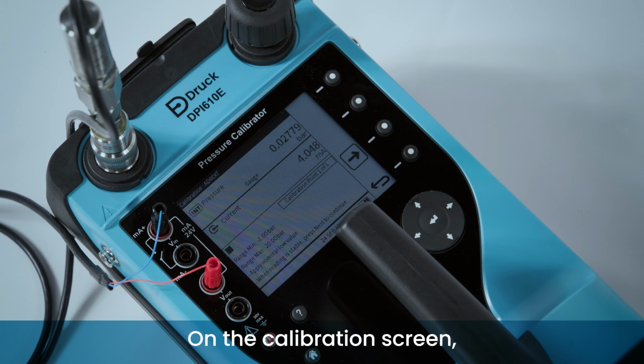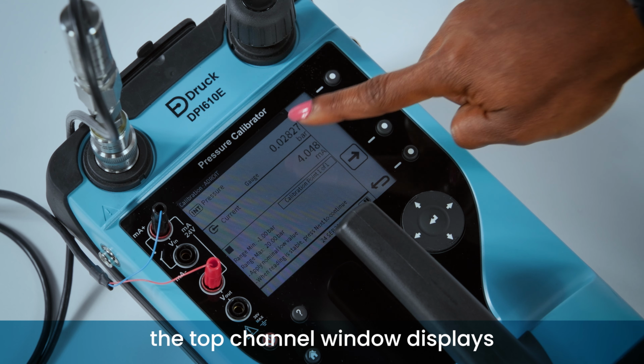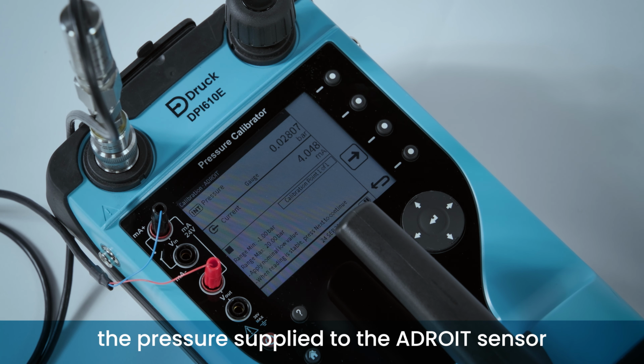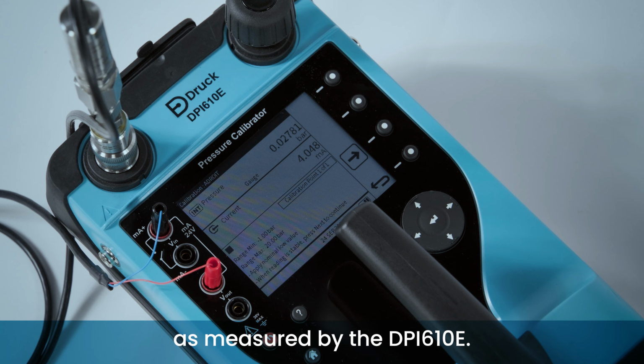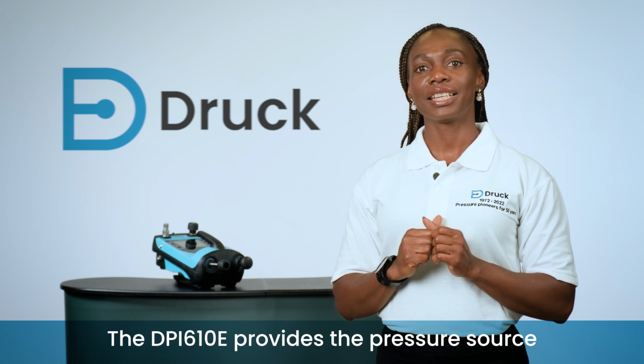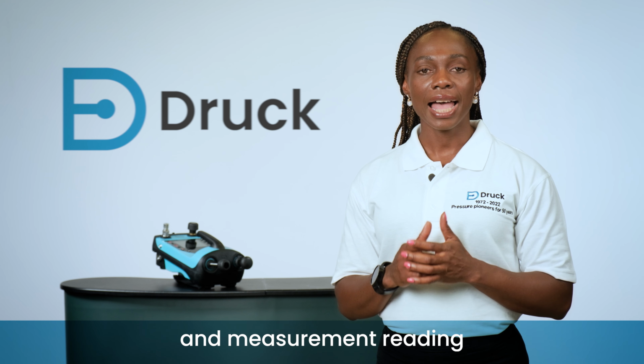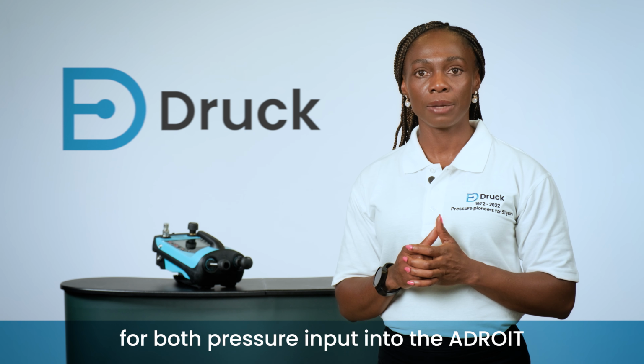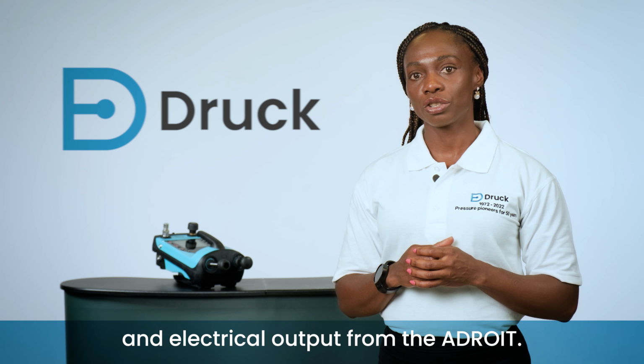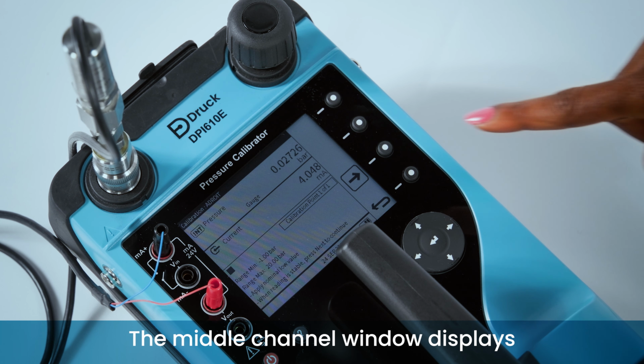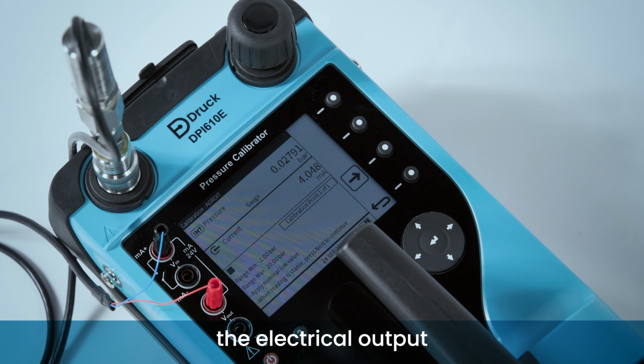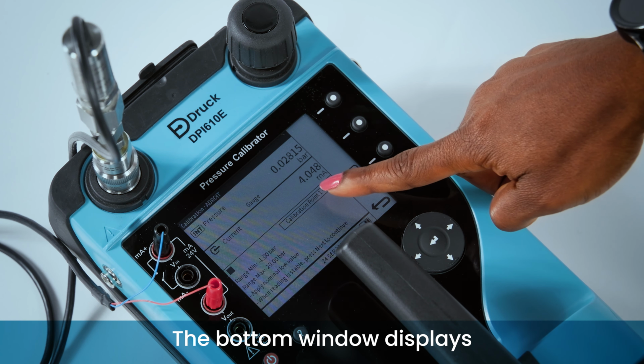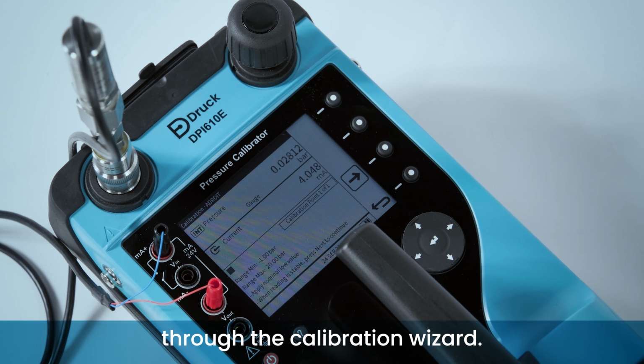On the calibration screen, the top channel window displays the pressure supplied to the ADROIT sensor as measured by the DPI610E. The DPI610E provides the pressure source and measurement reading for both pressure input into the ADROIT and electrical output from the ADROIT. The middle channel window displays the electrical output measured from the ADROIT. The bottom window displays information that guides the user through the calibration wizard.